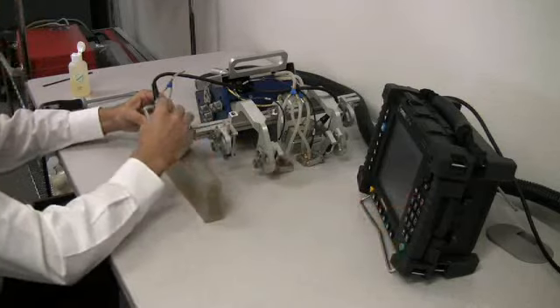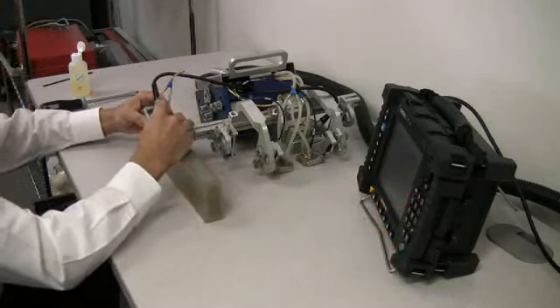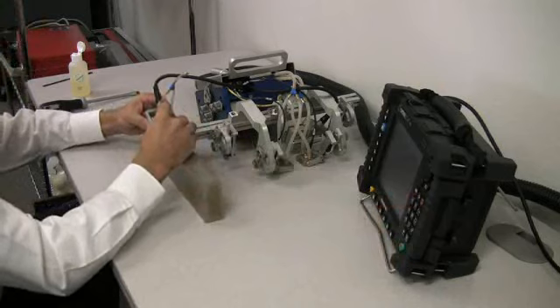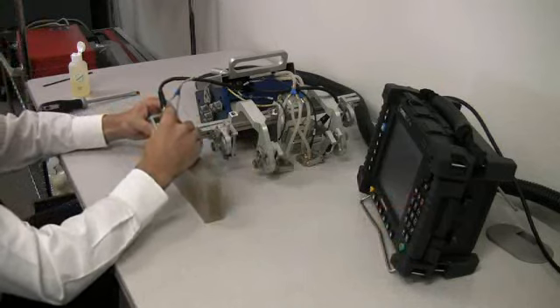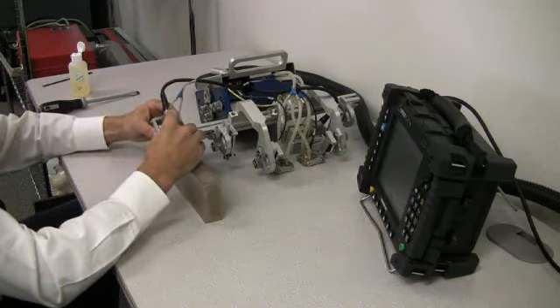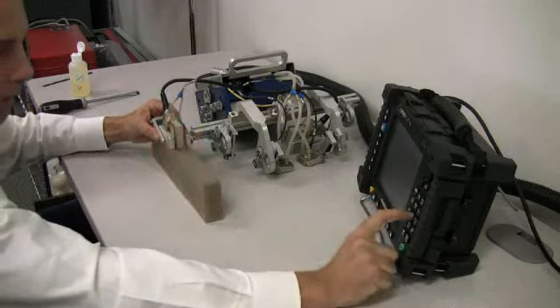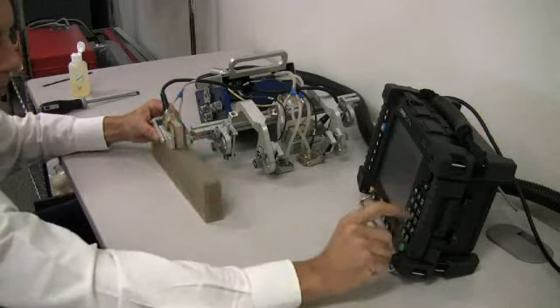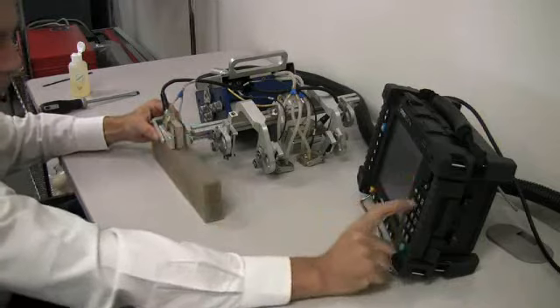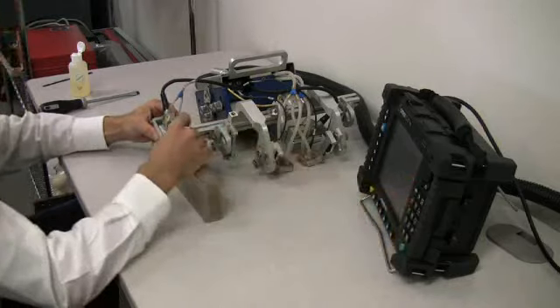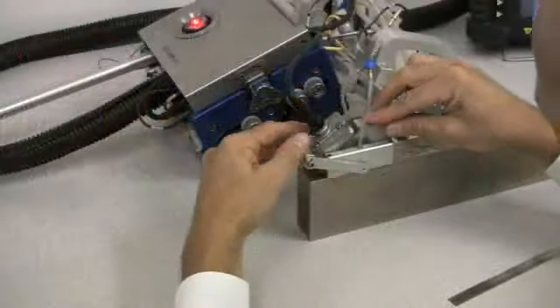We take our first calibration point, or TCG point, and take a nice, smooth acquisition. Use the auto calibrate feature. Move the gates to the next target. Back the probe up.